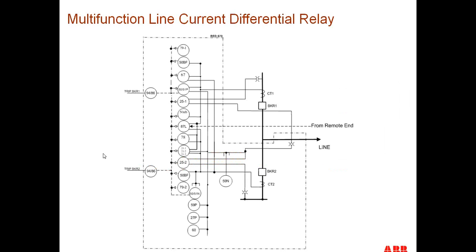Here's an example of a multifunction line current differential relay, just as an example of the types of things that we have in modern relays now. If you have a two-breaker scheme like you see here, we have CTs coming in separately from each of the breakers. So each breaker has its own breaker failure relay built into it. Each breaker has its own reclosing relay built into it, and sync check relay built into it.